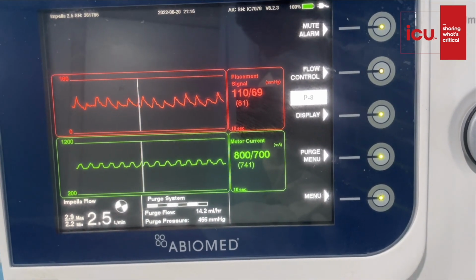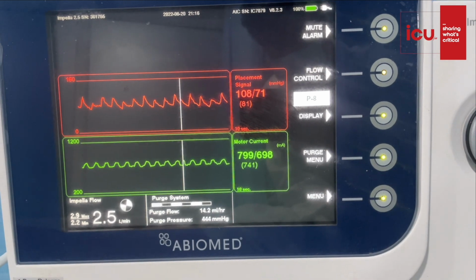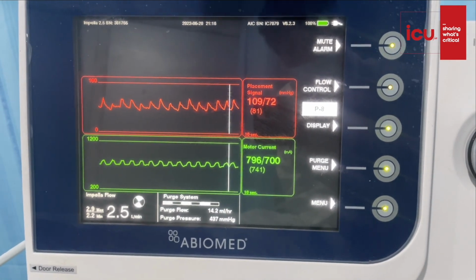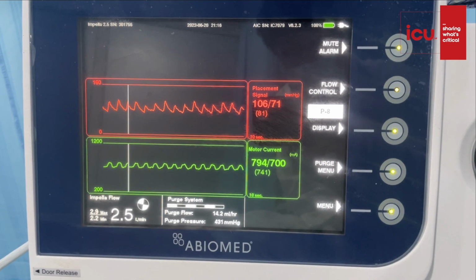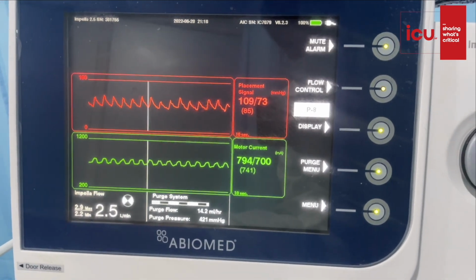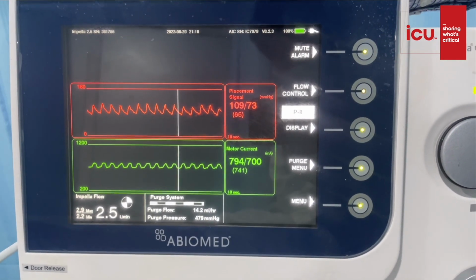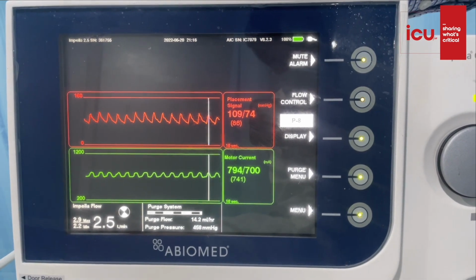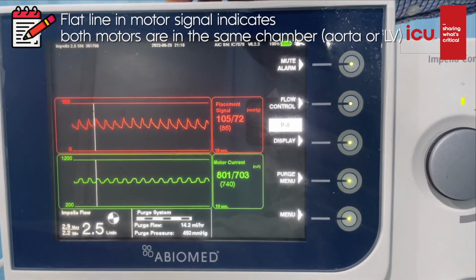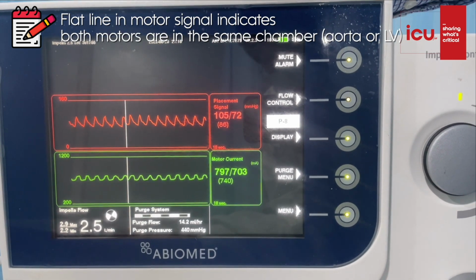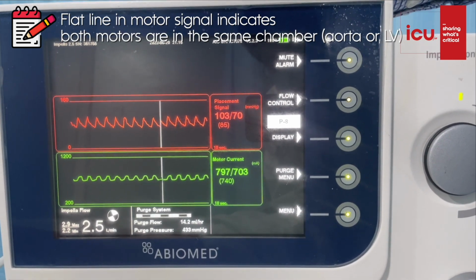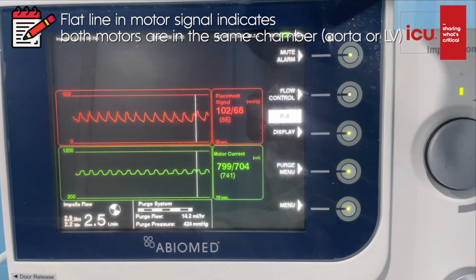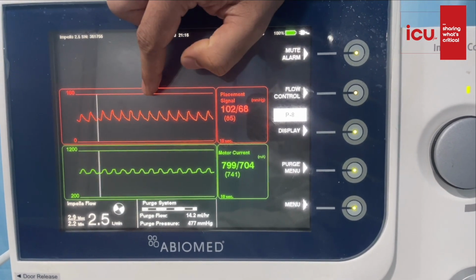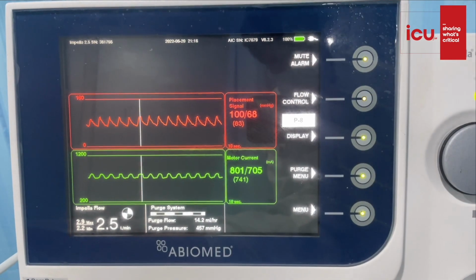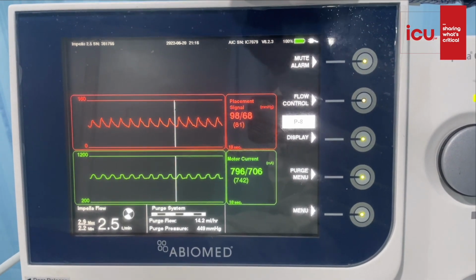Now as a clinician, how should this matter to you? In an ideal scenario, this motor current should always be pulsatile. When you see the motor current is flat, it means both the inlet and the outlet of the Impella device are in the same chamber. It can be in the LV or it can be in the aorta. That is completely wrong, and I need to adjust the position. So to summarize, the placement signal along with the motor current will help you to determine the right position of the Impella device. Now let's come further down.